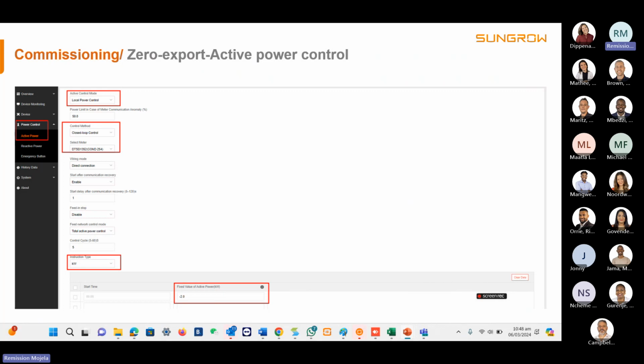And then for zero export, like I was explaining in the beginning, you have to use closed loop control and the meter. And then at the bottom, one important thing to do is you can also have a fixed value that is coming from the grid, whereby you can use a negative value. If it's -2, the system will constantly draw 2 kilowatts from the grid before production. After that, that's when the inverter will only produce after you are drawing more than 2 kilowatts coming from the grid, according to the setup that was done here on the system. You don't need to enable the feed-in limitation. You just have to set the system exactly like this.